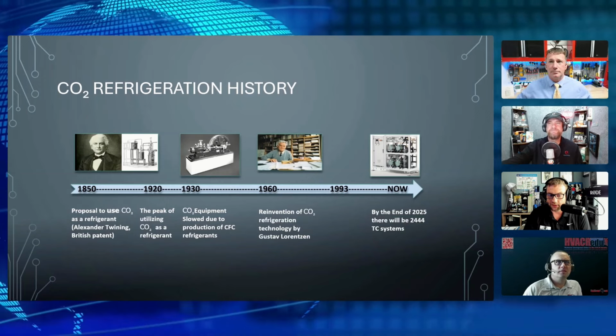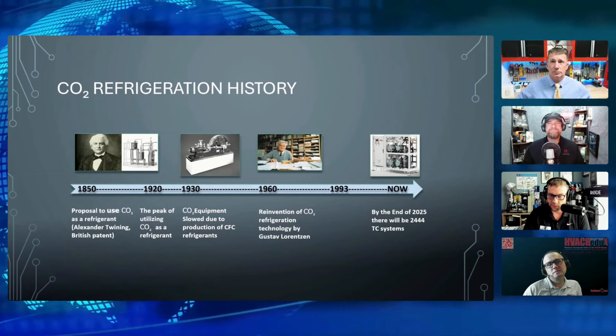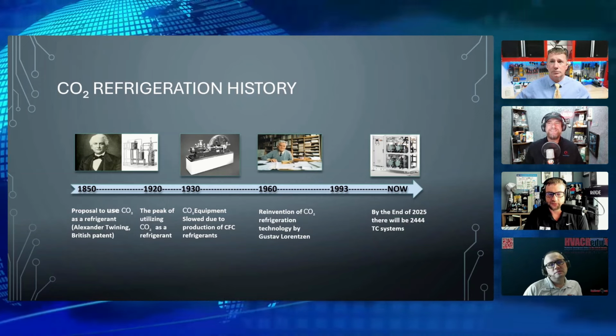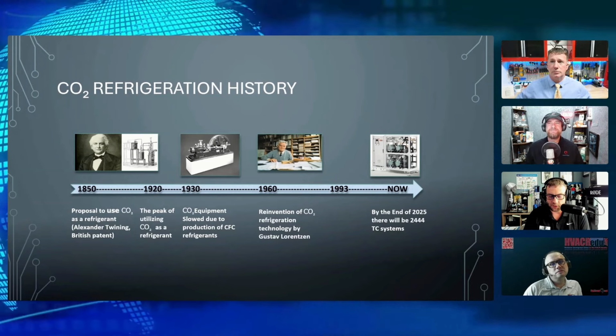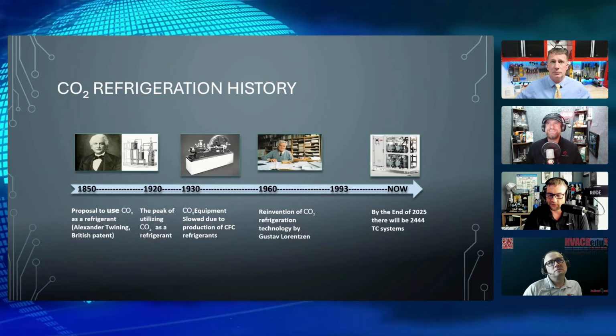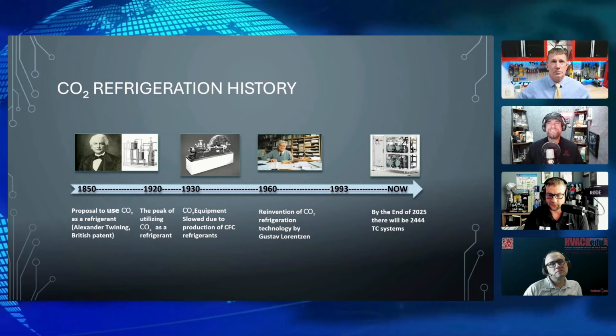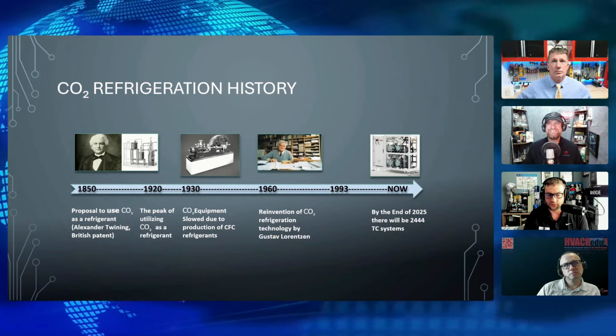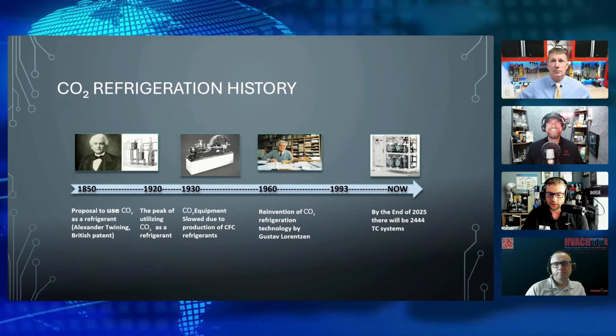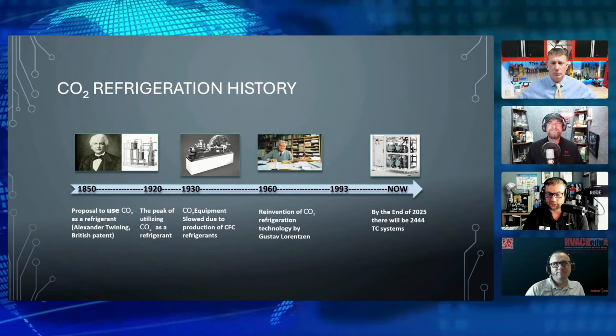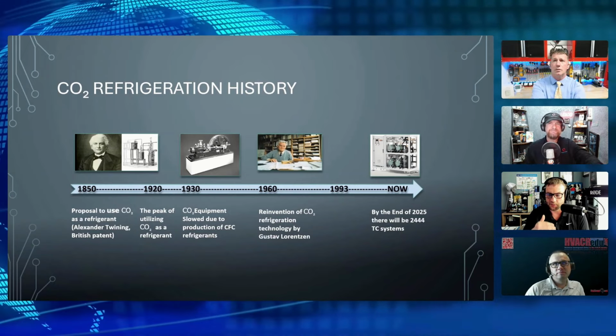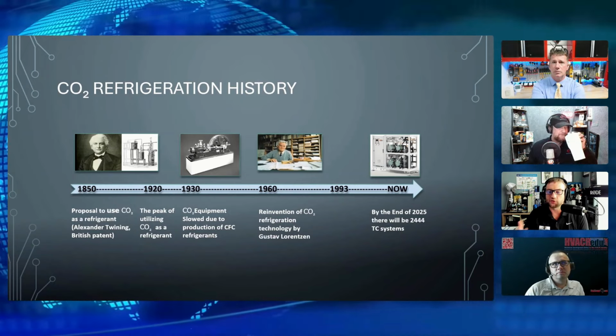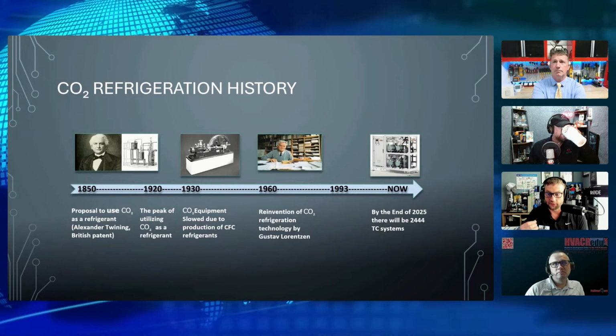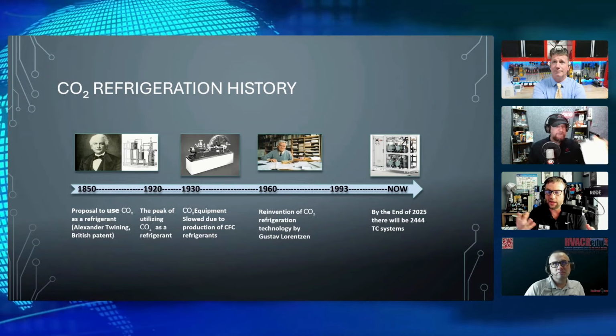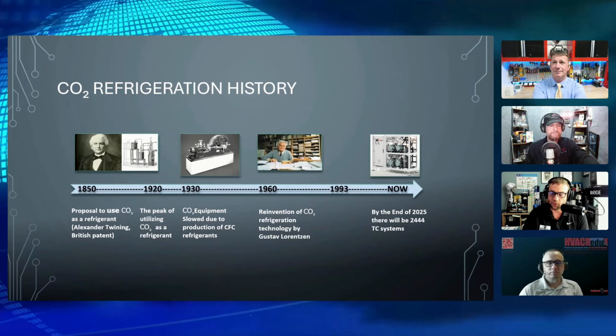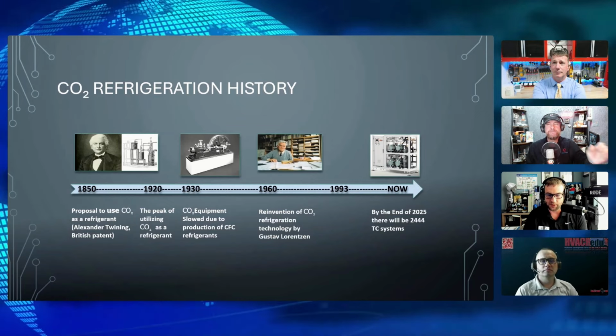After that, they said, well, these chemical refrigerants are a little bit easier to work with. Let's stop using CO2. It's the intricacies of control, and like I said, we'll get into that a little bit. One of the main differences between chemical refrigerants and CO2 is that CO2 has a very, very low critical point. What that means is that we operate at a point where it's basically the Schrodinger's cat of refrigeration. We don't know, is it a liquid? Is it a solid? Is it a vapor? It could be anything at that point. So we have to mitigate our control strategies based off of that.